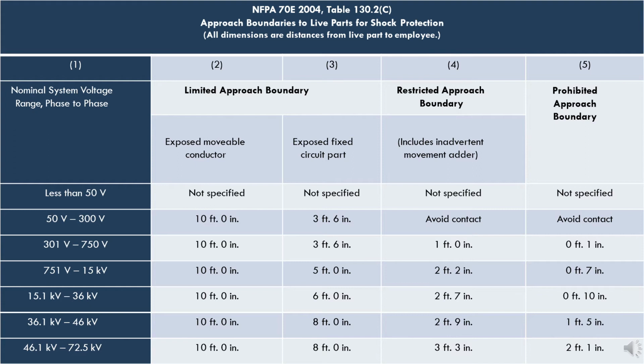Looking at the limited approach boundary, this is where the potential for electrical shock exists, and where an unqualified electrical worker must stop. There are two different distances in this table, but to make it universal and easily understood, no one should be within 10 feet of any electrical source without proper PPE. So at no point should anyone be within the limited approach boundary, restricted approach boundary, prohibited approach boundary, or within 10 feet of any energized circuit.